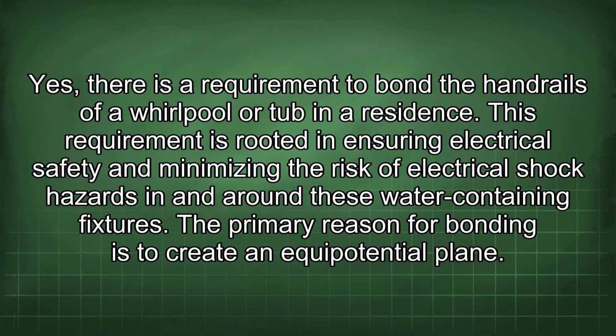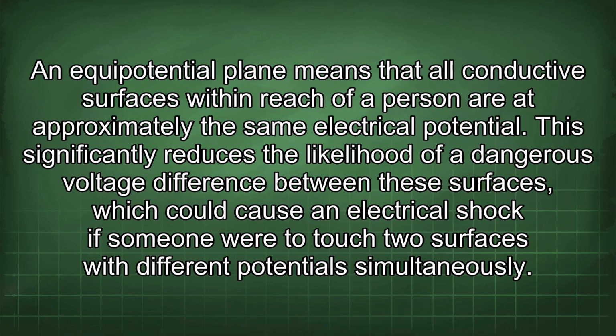Yes, there is a requirement to bond the handrails of a whirlpool or tub in a residence. This requirement is rooted in ensuring electrical safety and minimizing the risk of electrical shock hazards in and around these water-containing fixtures. The primary reason for bonding is to create an equipotential plane. An equipotential plane means that all conductive surfaces within reach of a person are at approximately the same electrical potential. This significantly reduces the likelihood of a dangerous voltage difference between these surfaces, which could cause an electrical shock if someone were to touch two surfaces with different potentials simultaneously.